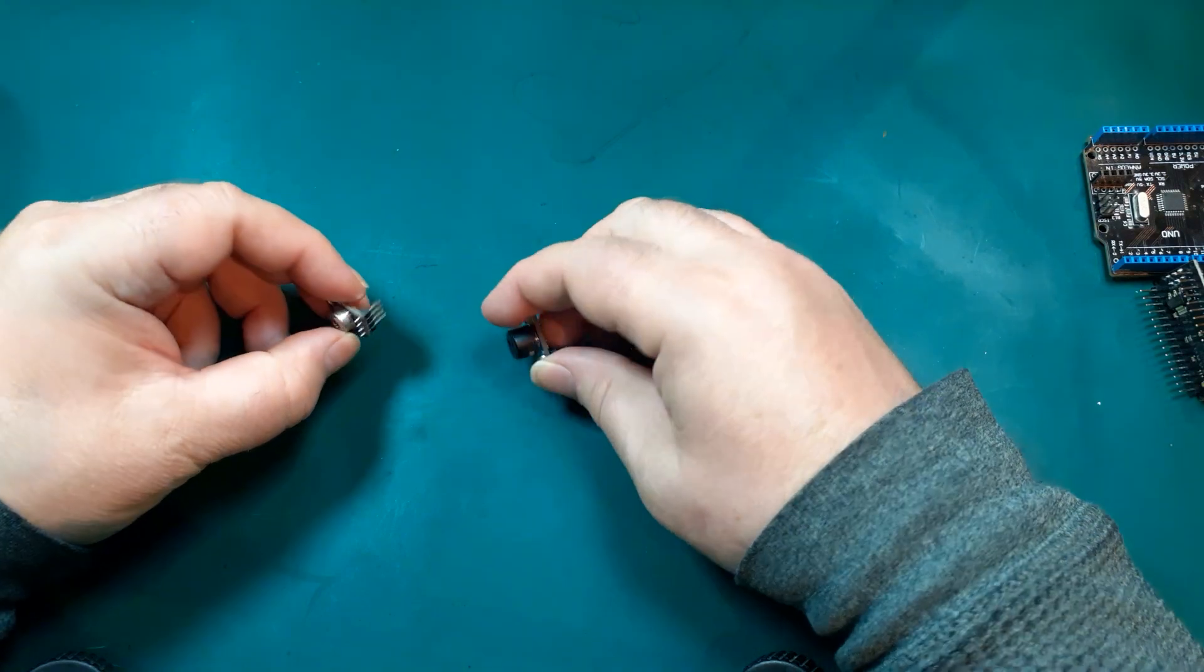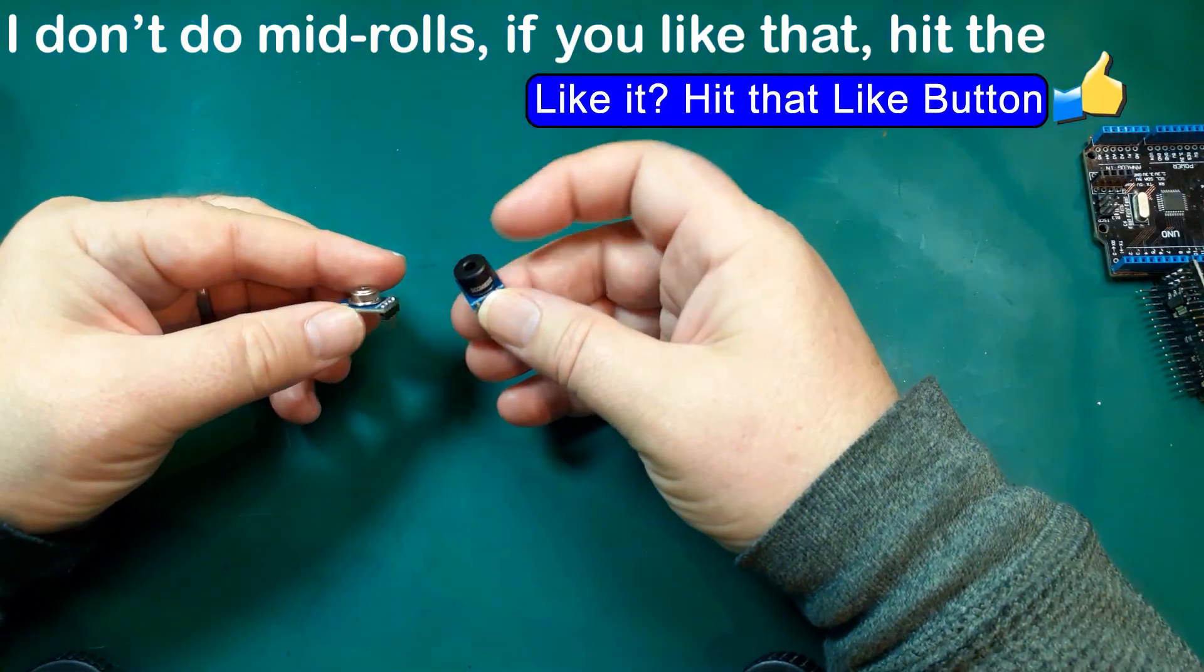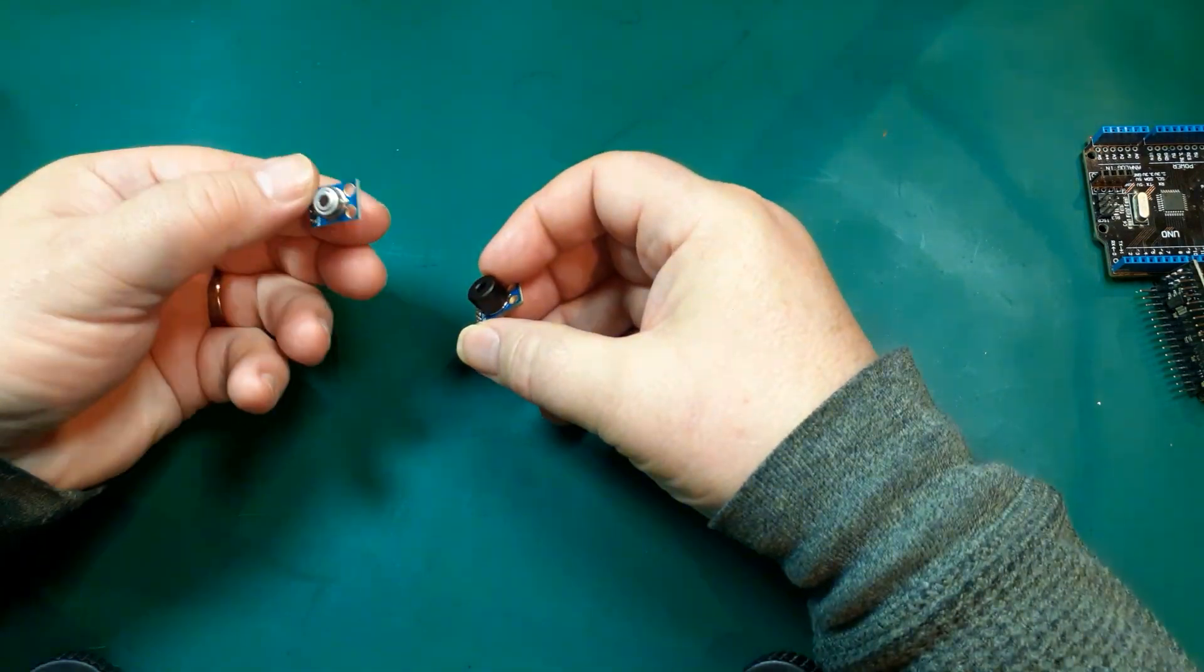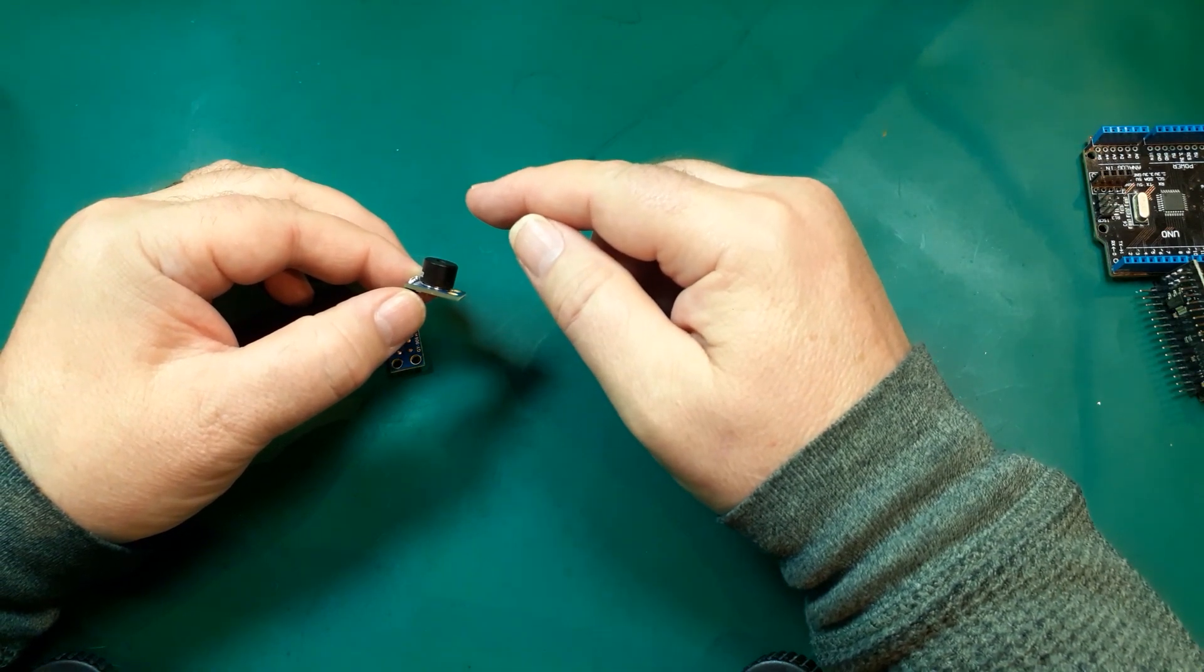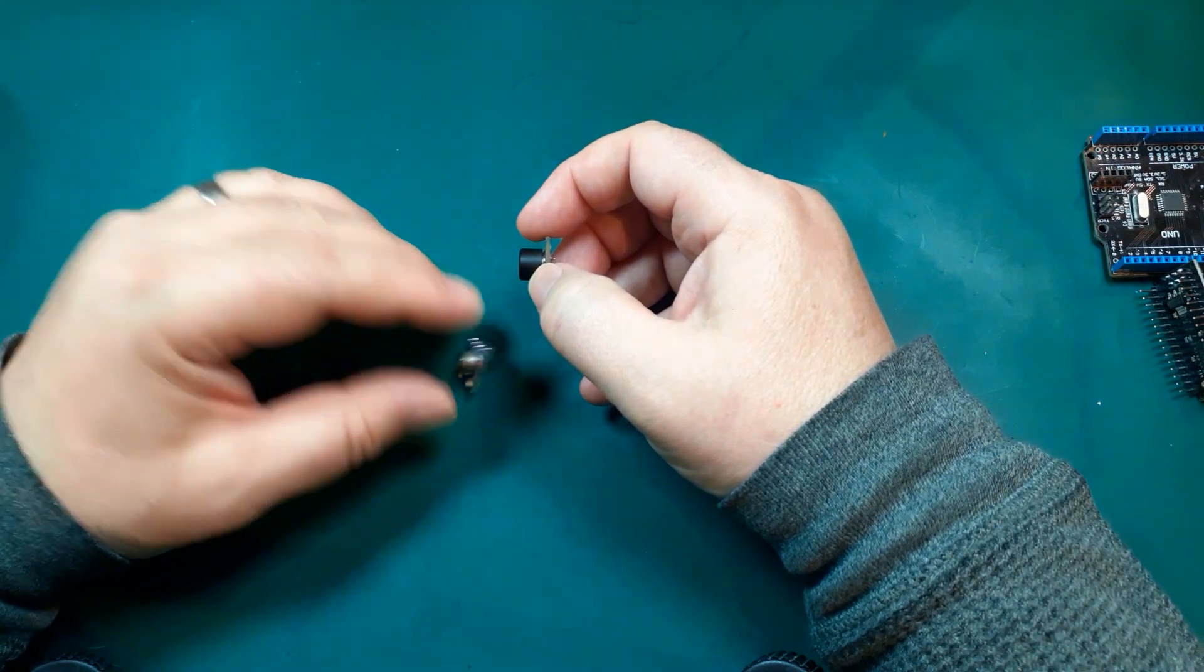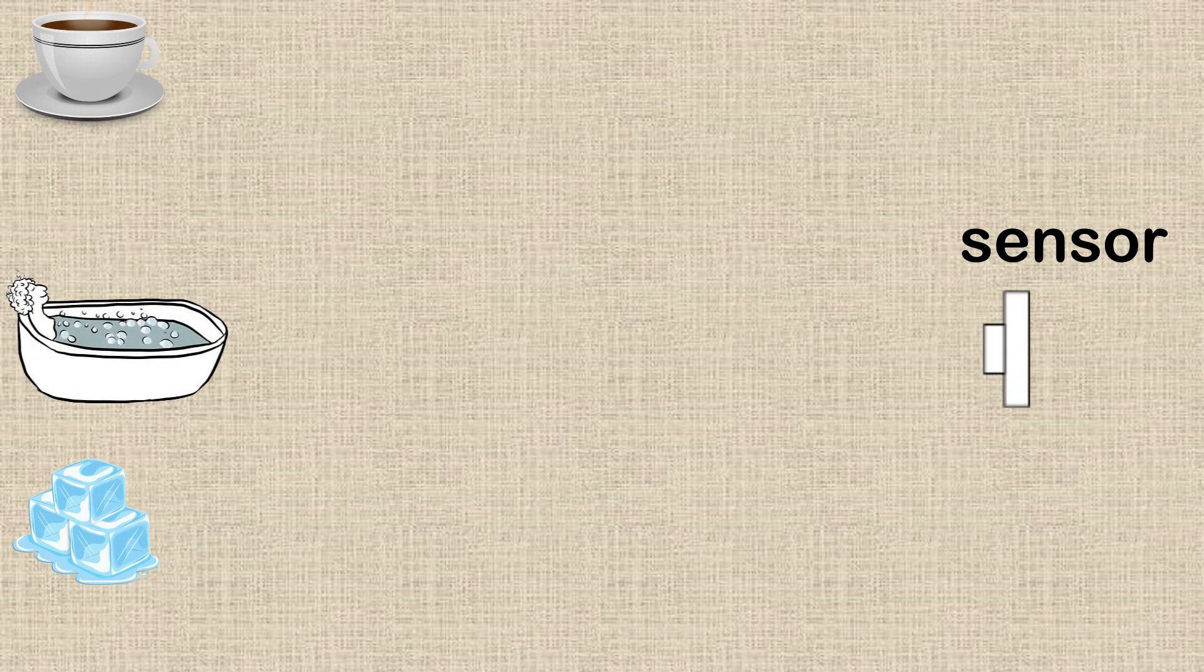You can see there are two obvious differences - one has this sort of shroud on and one doesn't. You can buy them without shroud as you can see there, or with a small shroud, a medium shroud, or quite a long shroud of around an inch or so. What that does is it allows you to sense the temperature of something and only that something from a greater distance.